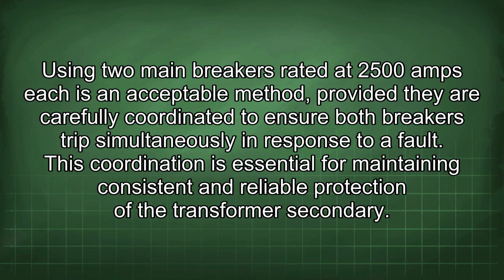Using two main breakers rated at 2500 amps each is an acceptable method, provided they are carefully coordinated to ensure both breakers trip simultaneously in response to a fault. This coordination is essential for maintaining consistent and reliable protection of the transformer secondary.